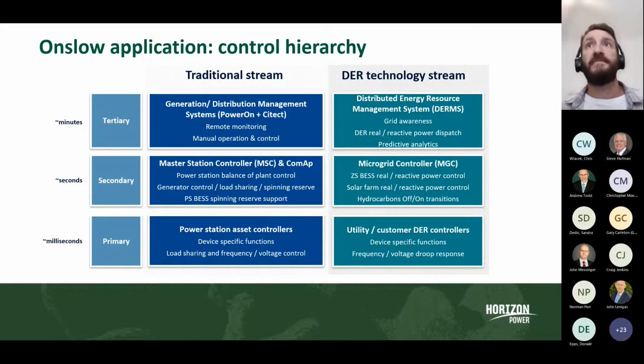Now the DERMS can consume a lot of data from the network, from the SCADA network and from IoT platforms and AMI metering systems to provide a level of grid awareness across the microgrid. From this information, it optimizes for a solution based on business rules and control objectives, and it schedules real and reactive power dispatch to each individual DER system.